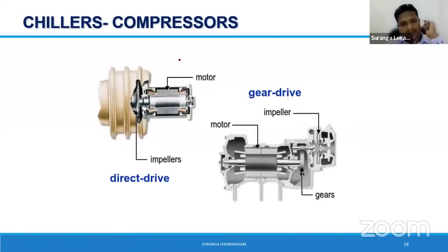Then the compressor. Referring to the centrifugal compressors, we can find direct drive versus gear drive, because all the motors used to drive the compressors are induction motors. For induction motors, the maximum RPM is 2,900 to 2,950 because of the slip. You can't reach 3,000. If you want higher compression speeds, the option is to go with gear drives. But with gear drives, there is a loss in energy as long as you have the gears. Therefore, there will be a slight compromise of efficiency in a gear drive machine compared with direct drive machines.